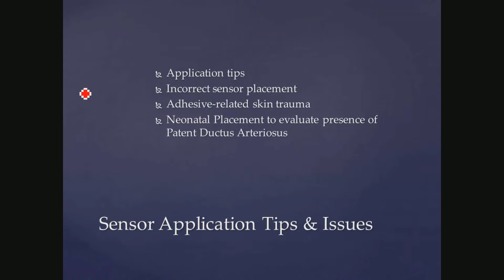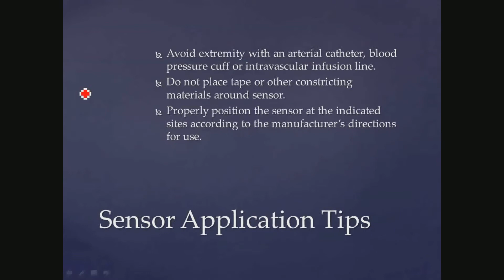Just incorrectly placing the sensor will give you some false readings. Just remember also about a PDA in the case of a neonatal patient. So some tips. Try not to use it with an arterial catheter, blood pressure cuff, or an intravascular infusion line. Try to use the alternative arm or hand. It should not be placed so that it's constricting. If you've ever put a Band-Aid on too tight, you felt that pulsatile flow. That's actually a venous pulse that you end up feeling. That's going to be interpreted as an arterial reading and can be a reason why your saturation is lower than it actually is. It's designed to be placed at a specific site.